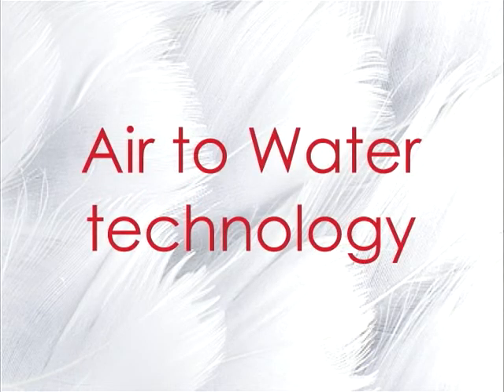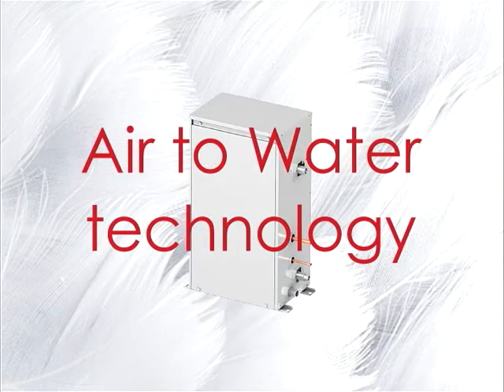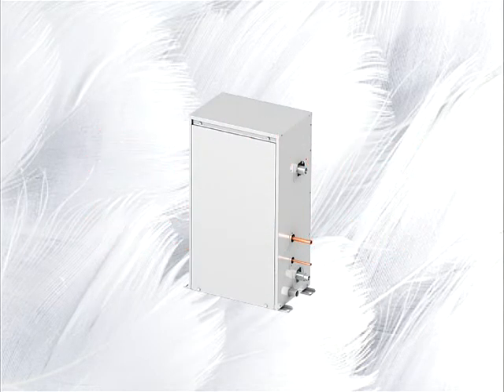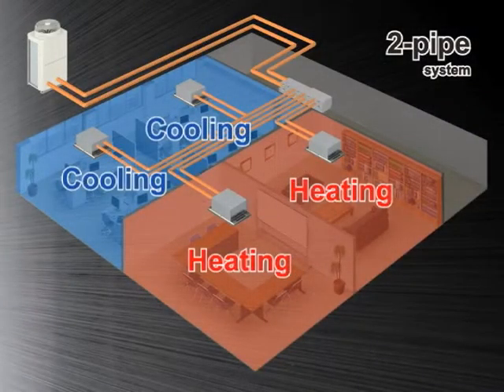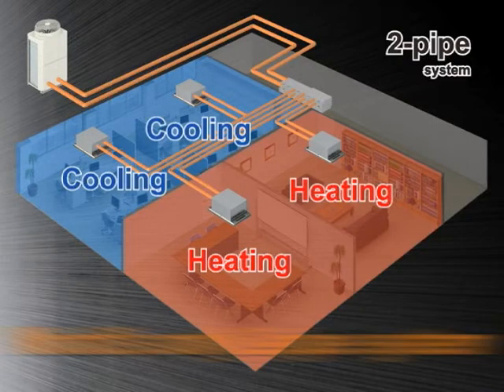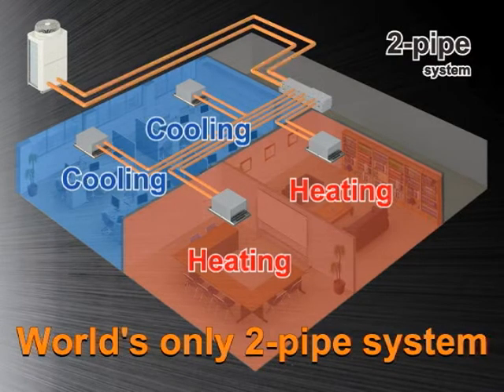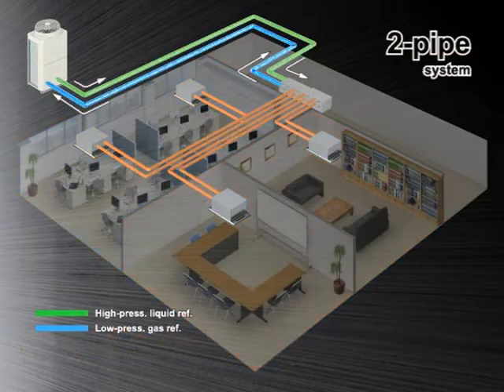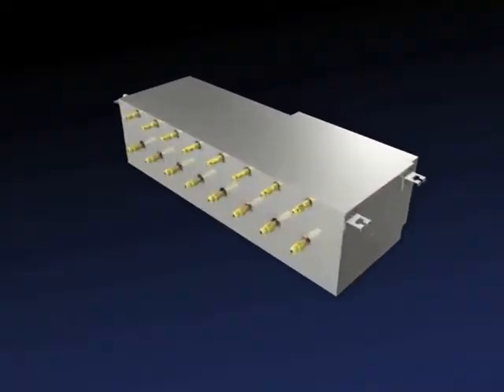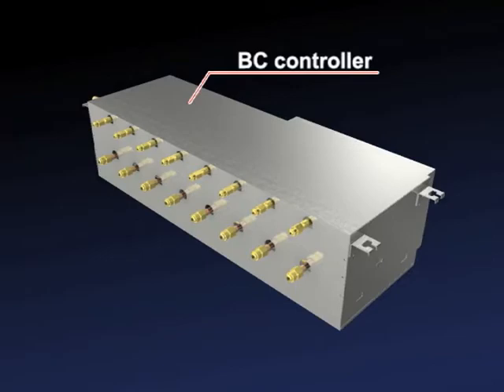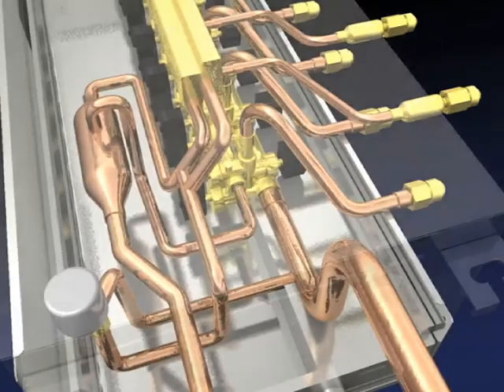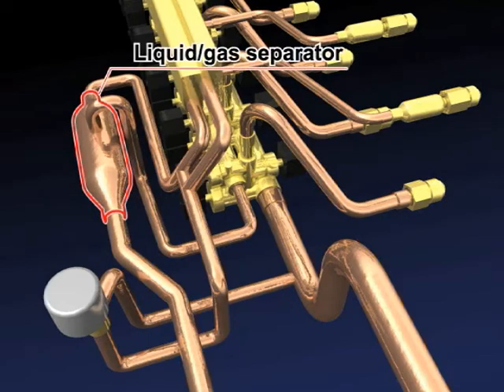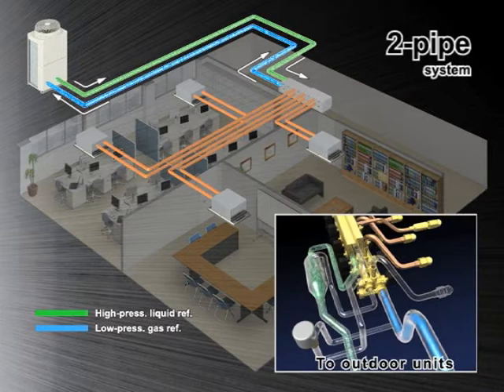Now, let's take a closer look at the intelligence of our air-to-water system. At the heart of our air-to-water technology is our R2 system. Our R2 system is designed for simultaneous heating and cooling with 2 refrigerant pipes, unlike the 3 pipes used in conventional market products. With the 2-pipe system, the BC controller houses a liquid and gas separator, allowing the outdoor unit to deliver a mixture of hot gas for heating and liquid for cooling, both through the same pipe.